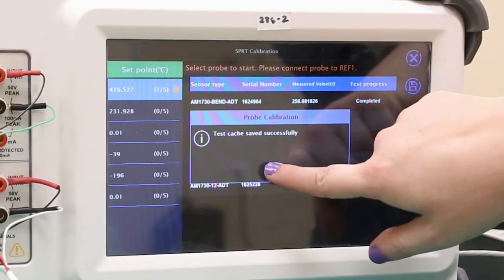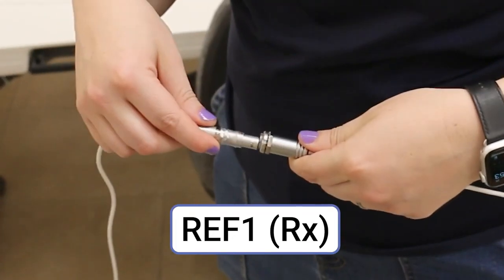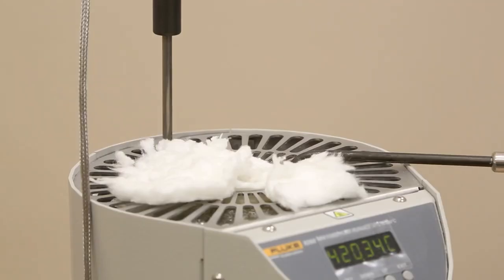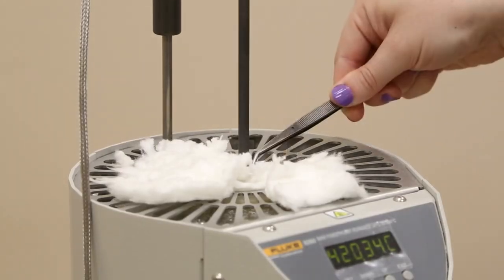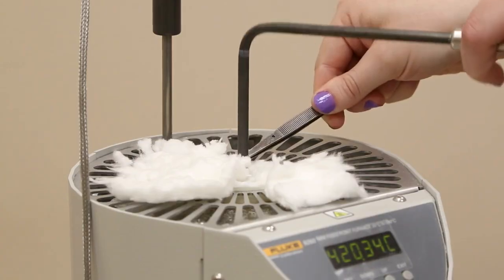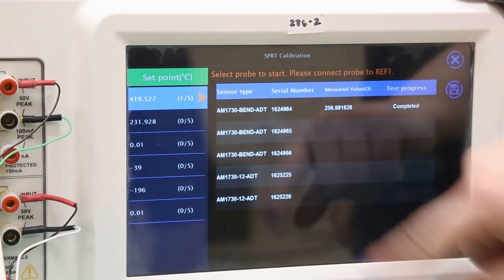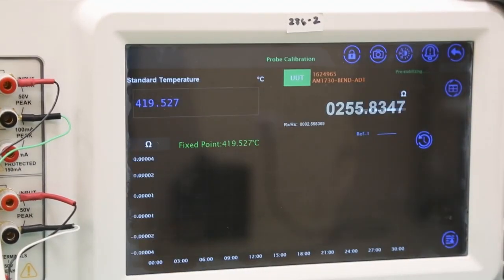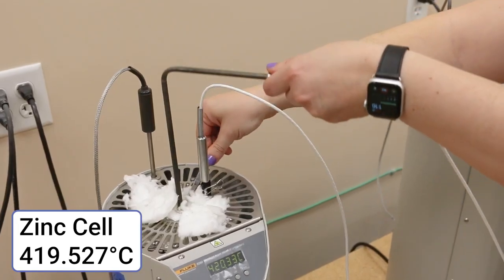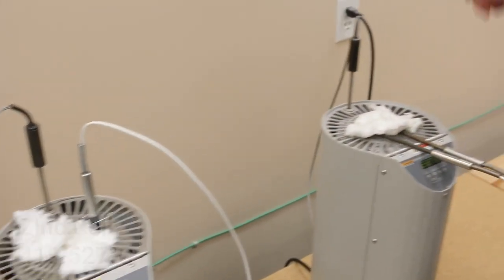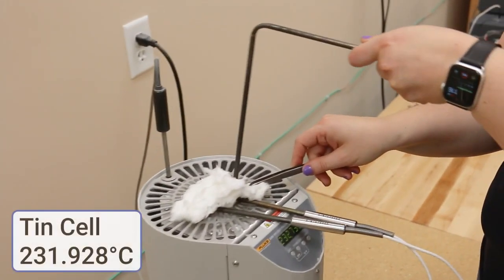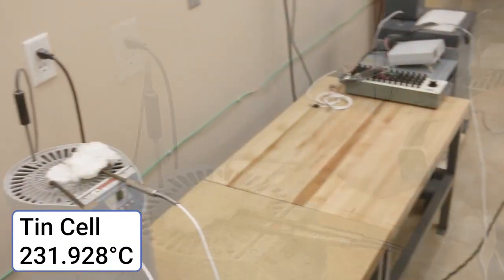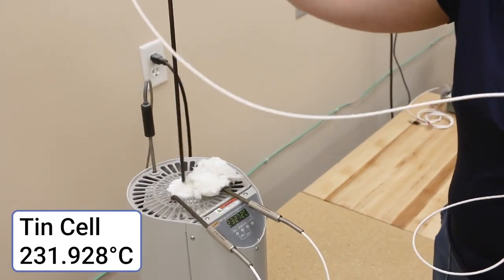Since we are calibrating the same probe types, we can swap between them using the quick connector. Now we will move the new probe to the active position on the zinc cell. Return to the 286 and select the second probe to begin measurement. These steps can be repeated for the rest of the probes. After measurement, the probes can be moved directly into the preheat well in the tin cell furnace to further reduce downtime. At any time, we can check the temperature of the tin cell as well.